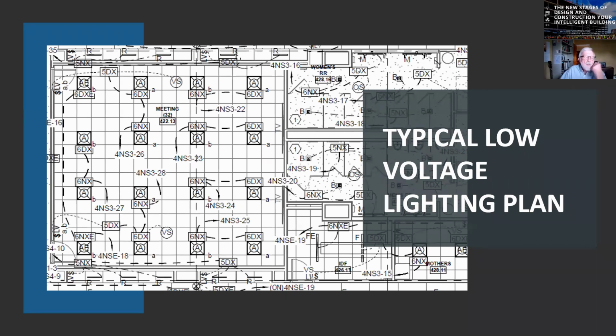This particular excerpt came from a fourth floor plan, so it's the fourth floor, and it's the normal power system, not emergency. The switch is switch three, and it goes to port 23 on the switch, so a person designing the structured cabling system can look at this and understand: I've got a cable that's going to go from here back to switch three, port 23. We're not showing how it gets there—we leave that for the low voltage designer and structured cabling designer, but we're giving you all the information you need to design that system.